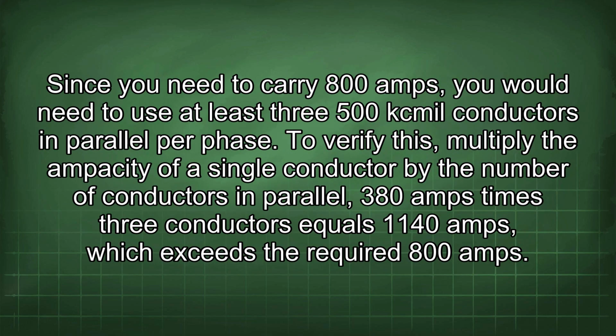Since you need to carry 800 amps, you would need to use at least 3 500 kcmil conductors in parallel per phase. To verify this, multiply the ampacity of a single conductor by the number of conductors in parallel. 380 amps times 3 conductors equals 1140 amps, which exceeds the required 800 amps.